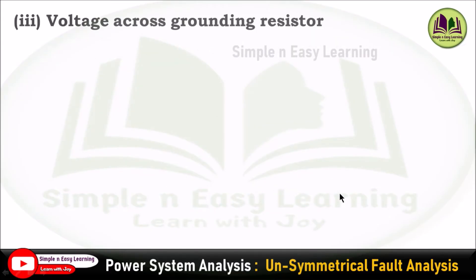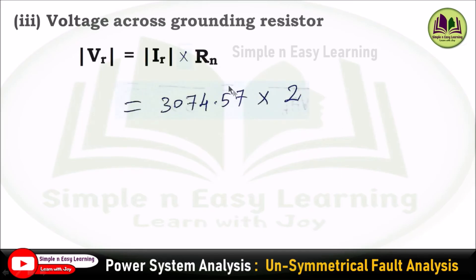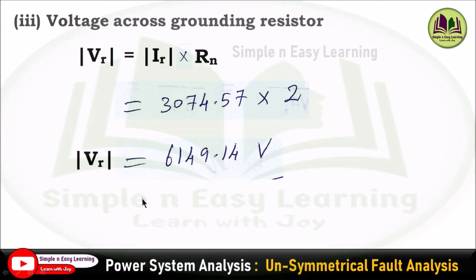Finally, determine the voltage across the grounding resistor. Knowing the current and resistance, simply multiply: VR = IR × Rn = 3074.57 × 2 ohm = 6149.14 volts.